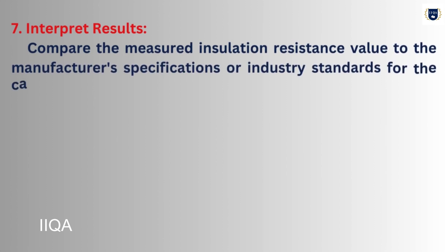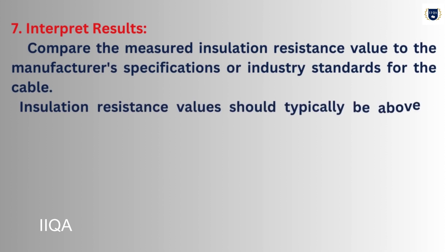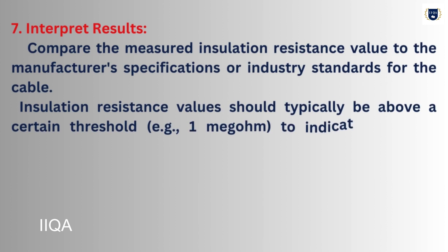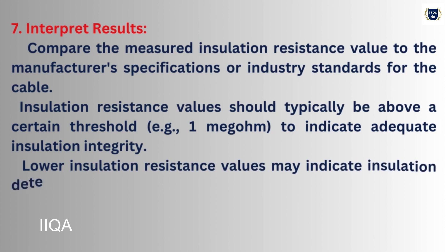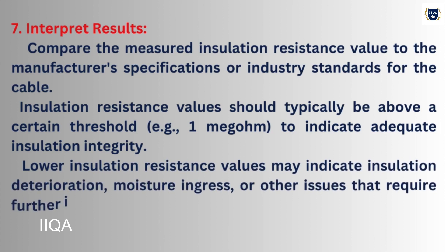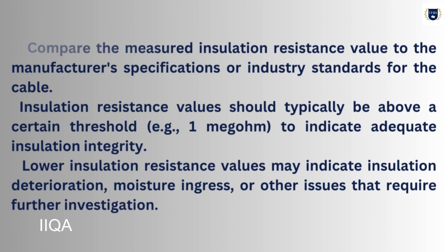Step 7 - Interpret Results: Compare the measured insulation resistance value to the manufacturer's specifications or industry standards for the cable. Insulation resistance values should typically be above a certain threshold, for example 1 megohm, to indicate adequate insulation integrity. Lower insulation resistance values may indicate insulation deterioration, moisture ingress, or other issues that require further investigation.